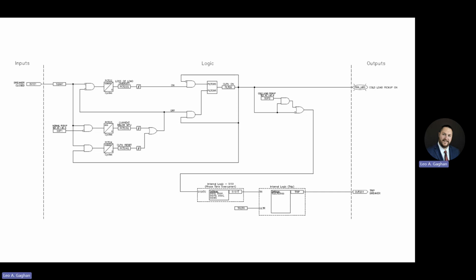So in this situation, we'll come through here. The breaker closed, this will be a 1. We'll have a 0 at this point of the logic. We don't have to worry about that. Come down here. We'll have a 0 here and a 0 here. So nothing is being asserted. Nothing's driving this latch, and it's off.